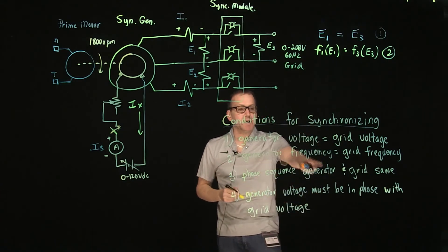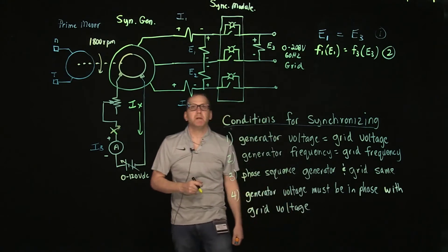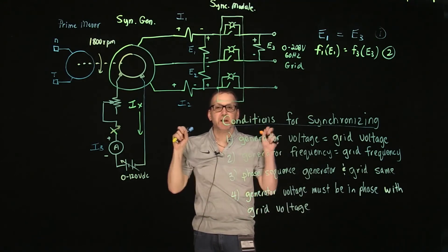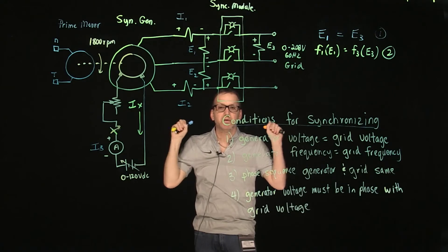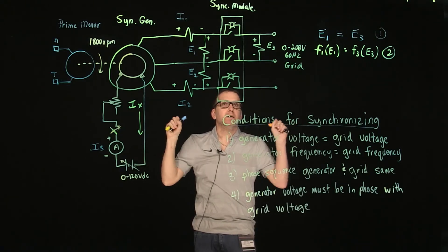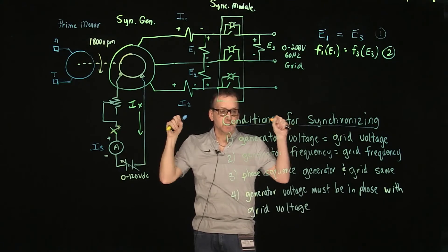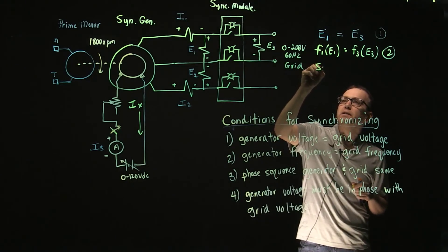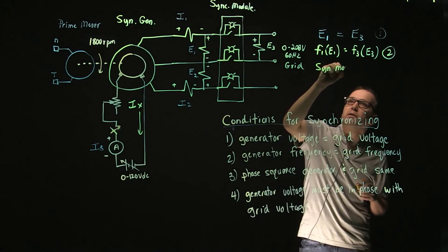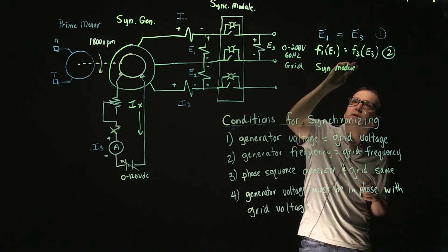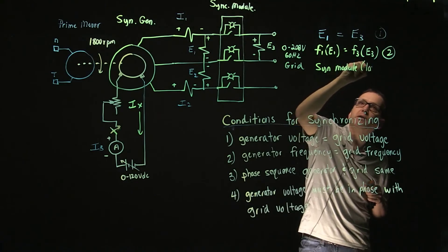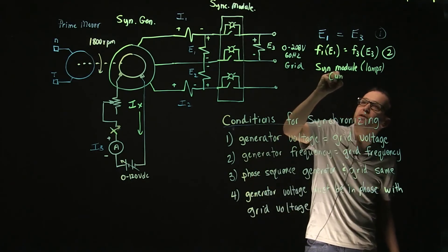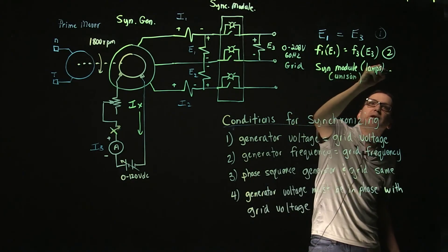For condition number three, the phase sequence of the generator and the grid must be the same. We can determine this by looking at the three lamps on the synchronizing module. If the three lamps are flashing in unison — going from light to dark all at the same time — the two systems have the same phase sequence.